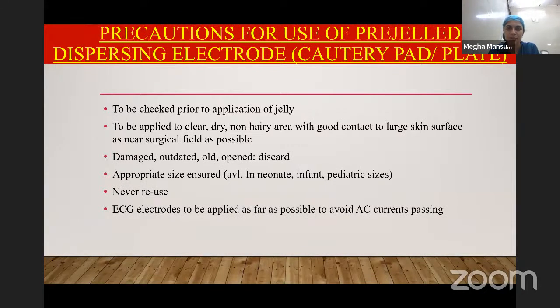Certain precautions should also be used when a pre-gel dispersing electrode is being used, which is the cautery pad. We should check it prior to application of jelly. We should apply it to a clean, dry, non-hairy area with good contact to a large skin surface as near the surgical field as possible. If this cautery pad is damaged, outdated, old or open, we should discard it and use another one. We should use pads of appropriate size. It is available in neonate, infant, and pediatric sizes as well. We should never reuse it. We should apply ECG electrodes as far as possible to avoid AC currents passing through them.